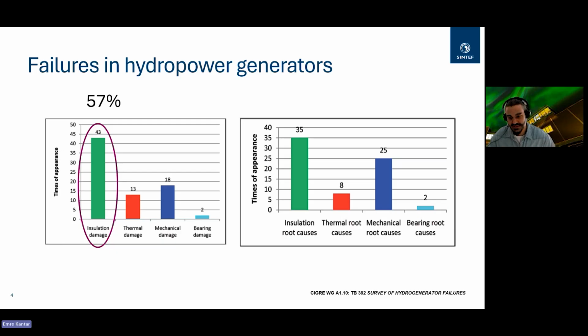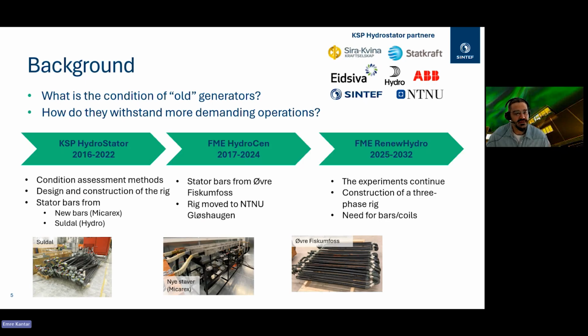According to some old statistics from Cigre, 57% of the recorded failures are due to insulation damage. This is the insulation used in the stator bars that carry the currents in the machines to generate the magnetic forces. So the background question is: what's the condition of the old generators given this intermittent operation, and can they withstand these more demanding operation strategies nowadays?